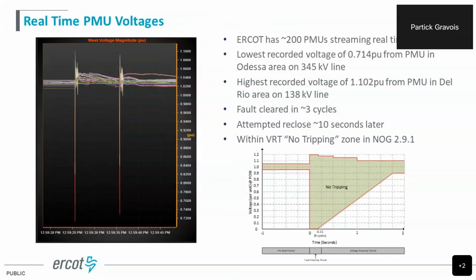So for this event, I've got some screenshots of some of our PMU data. So this is the real-time PMU data from West Texas. You can see there were 2 clear faults, the fault and then a reclose about 10 seconds later. The lowest voltage recorded out west was about 0.7 per unit from a PMU right near the fault on the 345 kV. The 138 kV, we saw the highest voltage of 1.1, but again, all of this was well within that no tripping zone that we have in our nodal operating guide requirement, section 2.9.1. There's a screenshot of that below. And again, the fault cleared normally within 3 cycles.